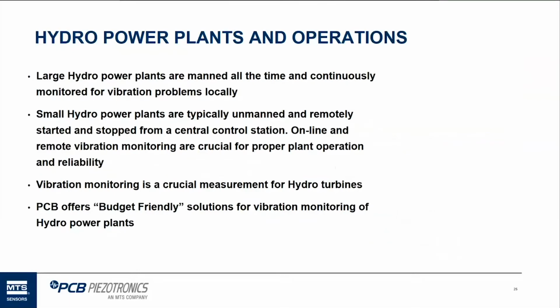So hydropower and operations, kind of going to talk about large versus small plants. Large plants, kind of like the sizes I showed you earlier at the top 10, even smaller than that, are manned all the time by people. They're always there, and they're monitored by full-time active vibration monitoring systems. So they can basically shut a large hydro unit off if it needs to be because the vibration level is really high.